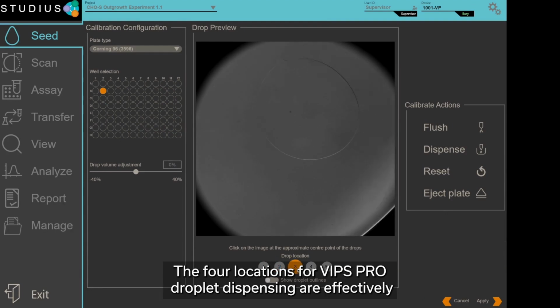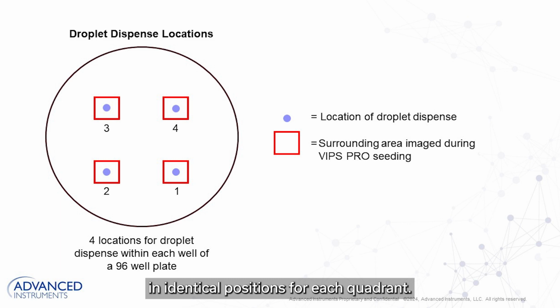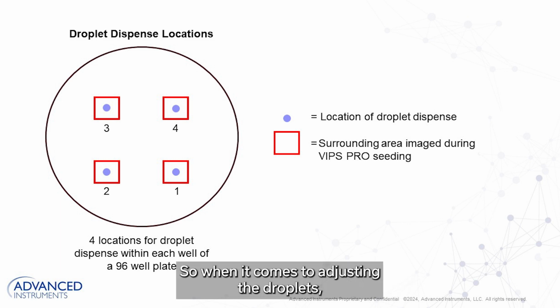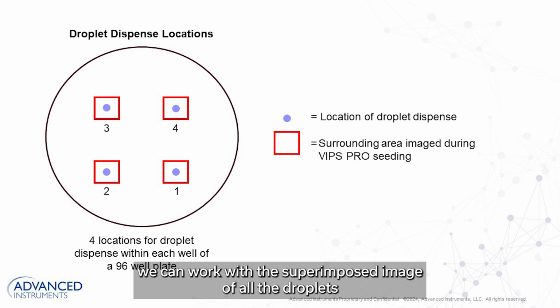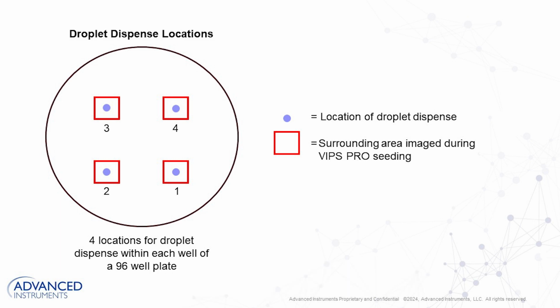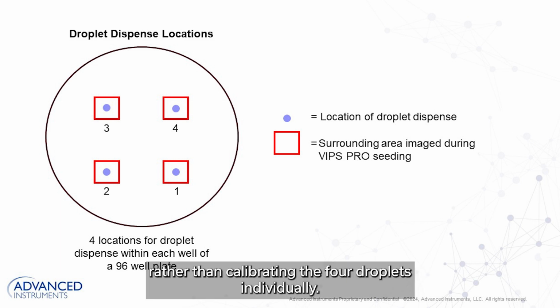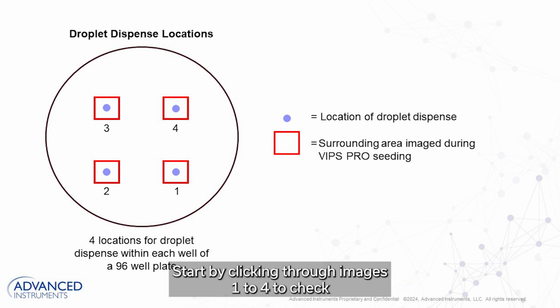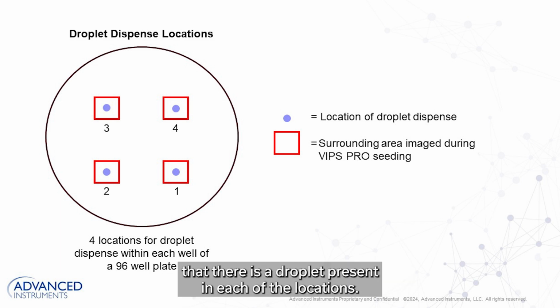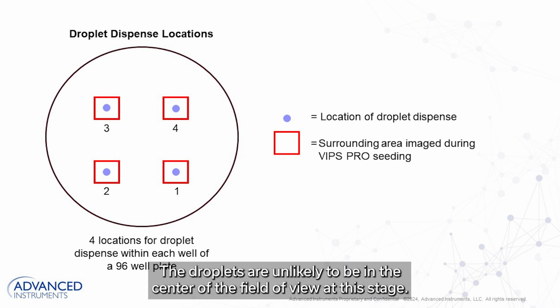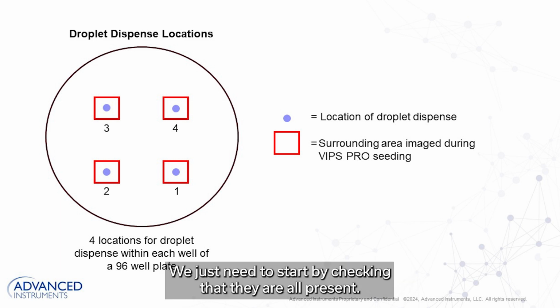The 4 locations for VIPS Pro droplet dispensing are effectively in identical positions for each quadrant, so when it comes to adjusting the droplets, we can work with the superimposed image of all the droplets rather than calibrating the 4 droplets individually. Start by clicking through images 1 to 4 to check that there is a droplet present in each of the locations. The droplets are unlikely to be in the center of the field of view at this stage. We just need to start by checking that they are all present.